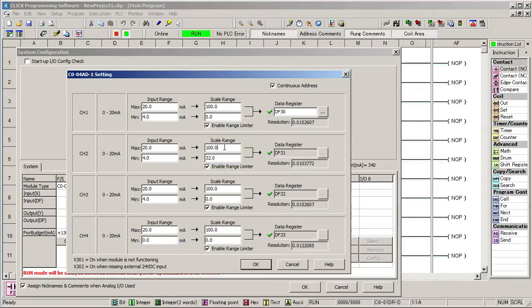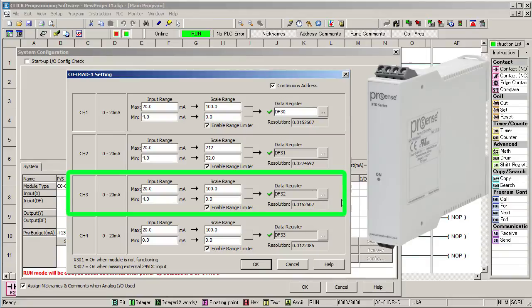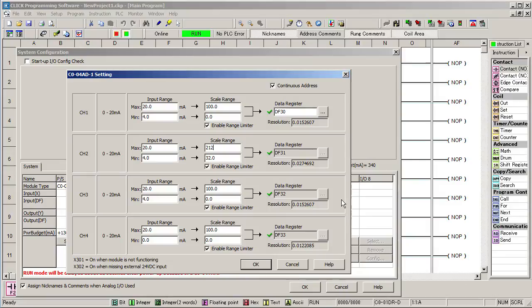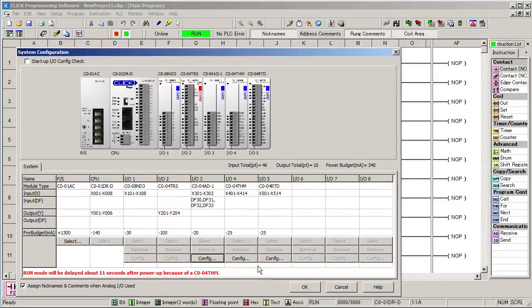The second temperature transmitter is an integral temperature transmitter and it's fixed at 0 to 100 degrees C which is 32 to 212 degrees F. And the third transmitter is a DIN-rail thermocouple type J module with a fixed output of 0 to 100 degrees F. And that takes care of our temperature transmitters.